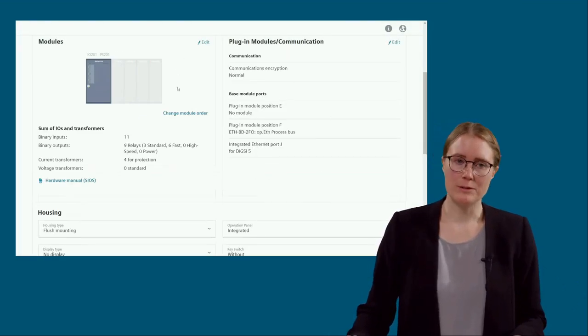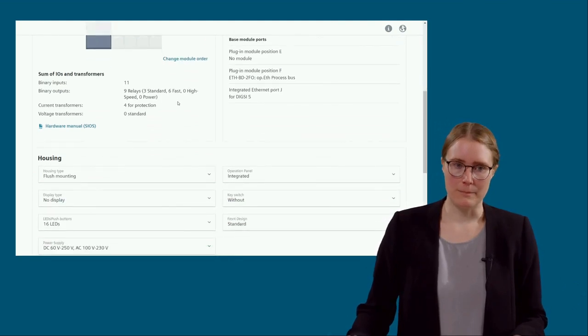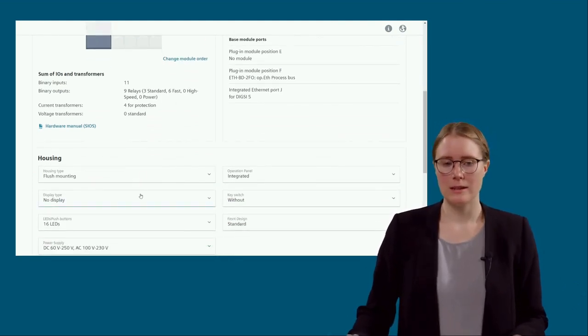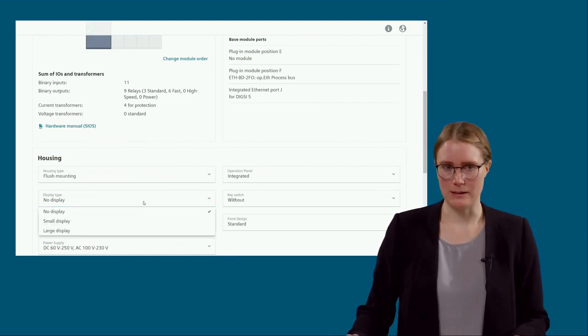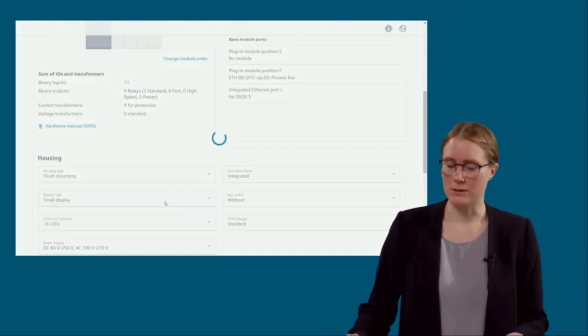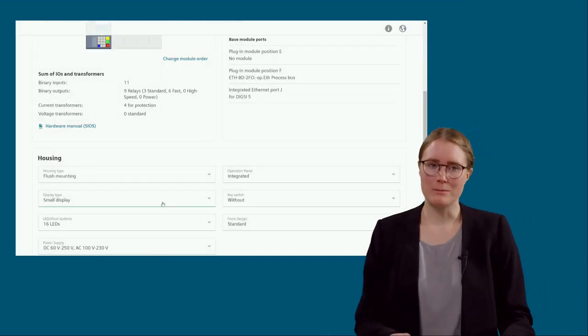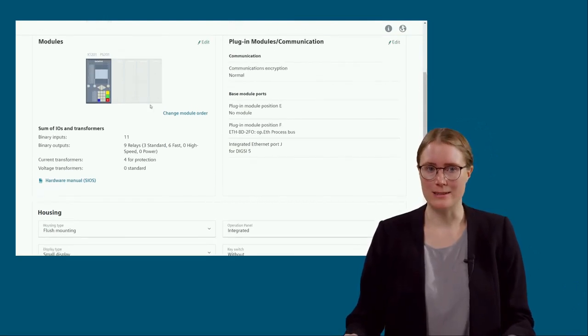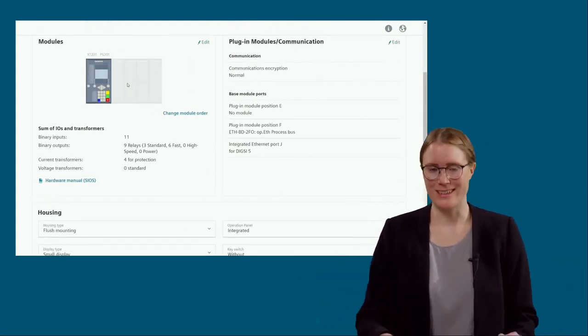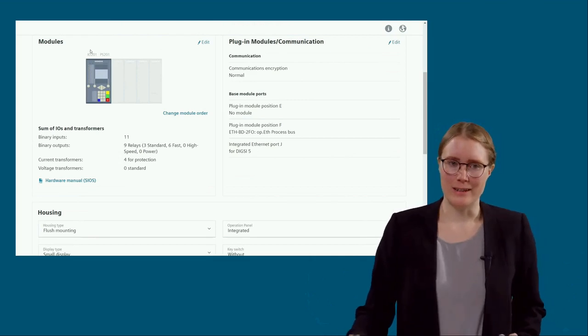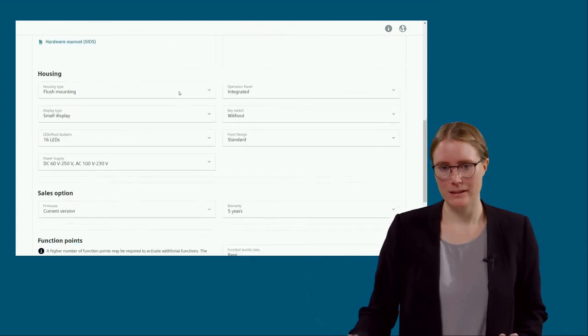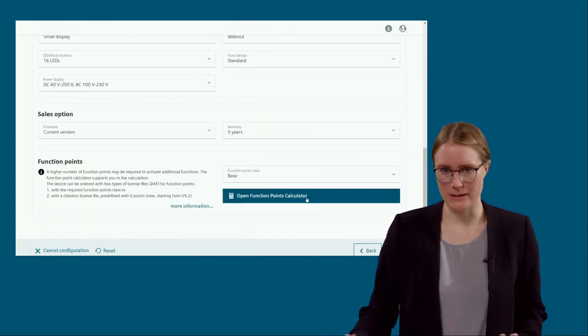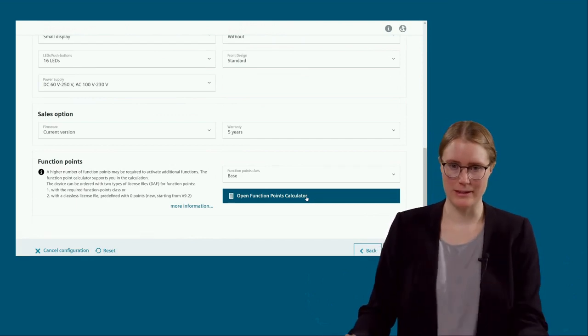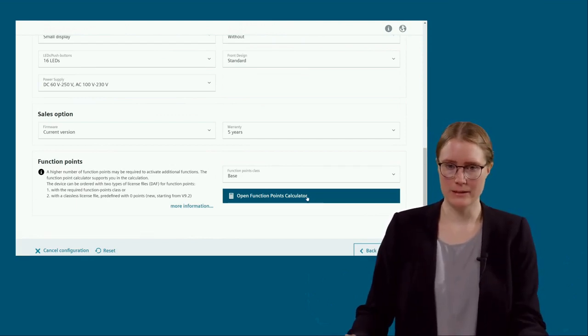Okay, here once again the overview of our merging unit. Here maybe it's worth mentioning that of course you can add a display to the merging units as well, a small one or a large one. In this case, maybe I go with a small one. And then it is possible to add some measuring signals or whatever you want, disconnector status, for example, already in the merging unit's HMI. Okay, but here, of course, the function points calculator would again be interesting.